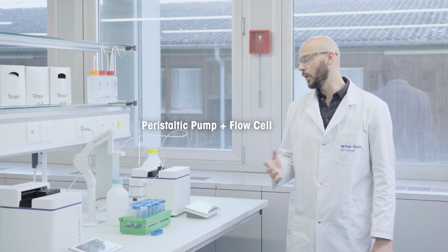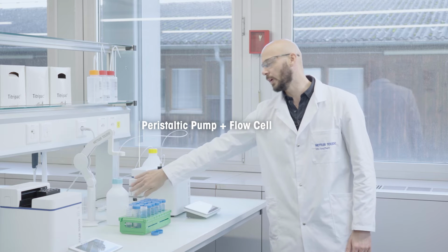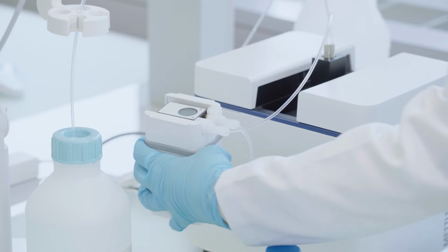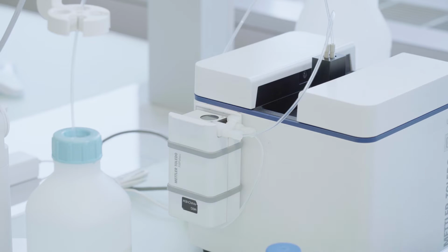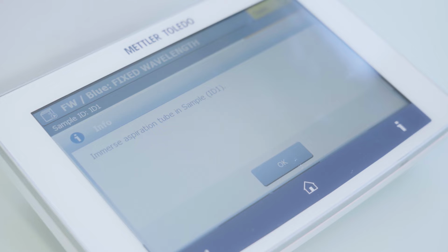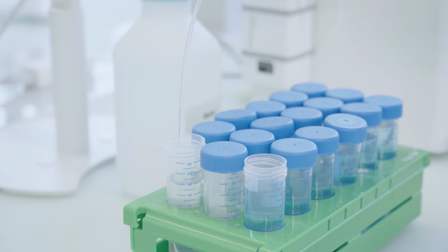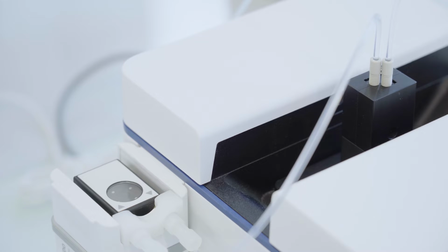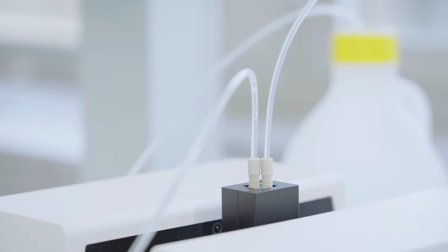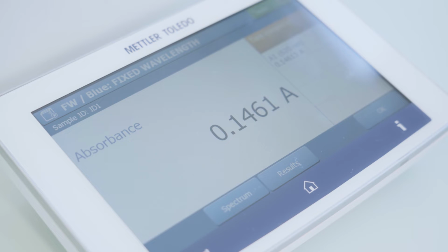When speaking of single sample automation, we can automate the analysis using peristaltic pumps. These are ideal to limit the exposure of operators to possibly hazardous samples and in general to reduce the number of manual steps needed to carry out the analysis. All you need to do is immerse the tube into the sample and the sample is transferred automatically to the flow cell for measurement.